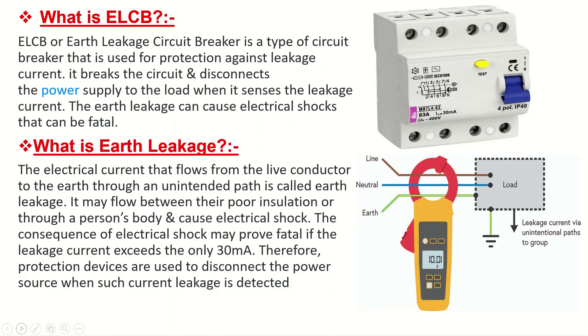What is Earth Leakage? The electrical current that flows from the live conductor to the Earth through an unintended path is called Earth Leakage. It may flow through poor insulation or through a person's body and cause electrical shock. The consequence of electrical shock may prove fatal if the leakage current exceeds only 30 mA. Therefore, protection devices are used to disconnect the power source when such current leakage is detected.